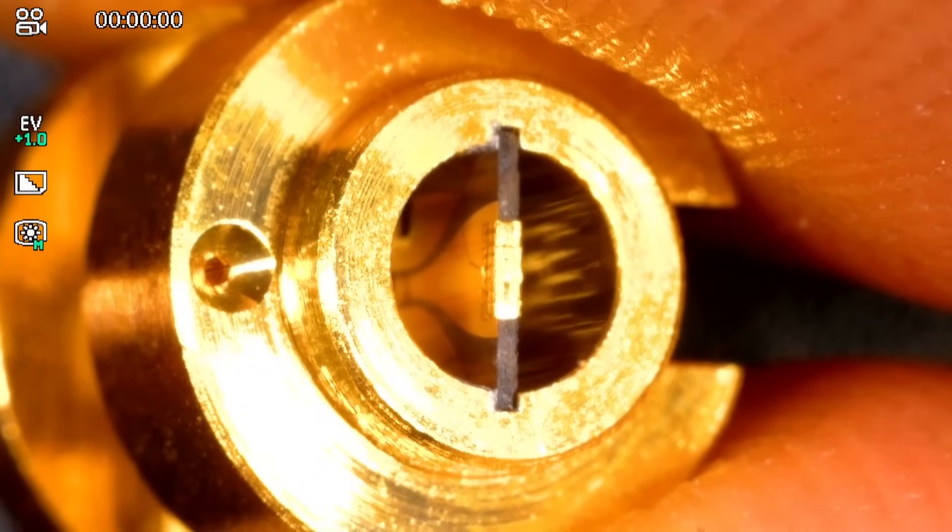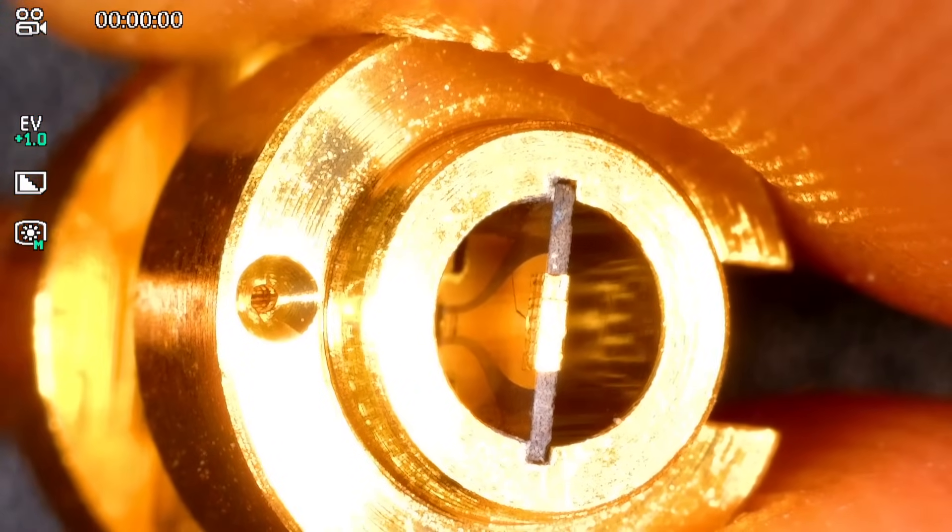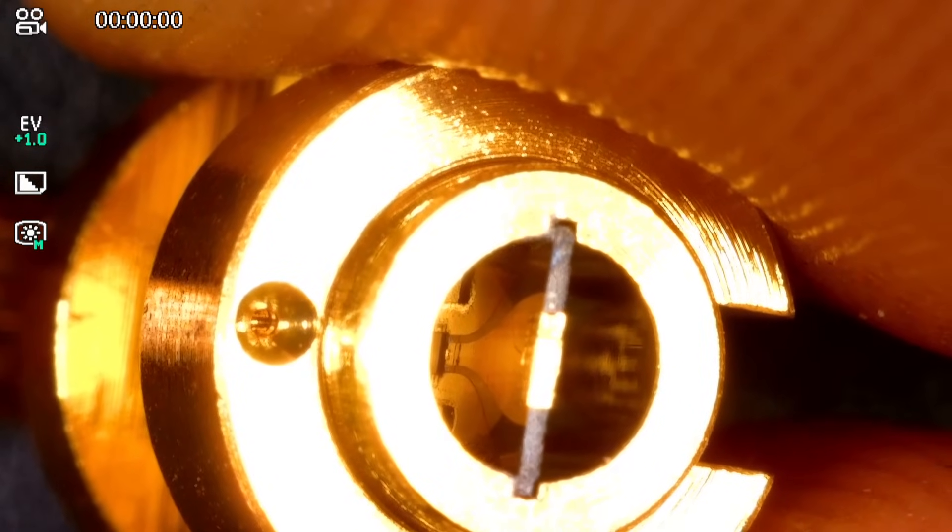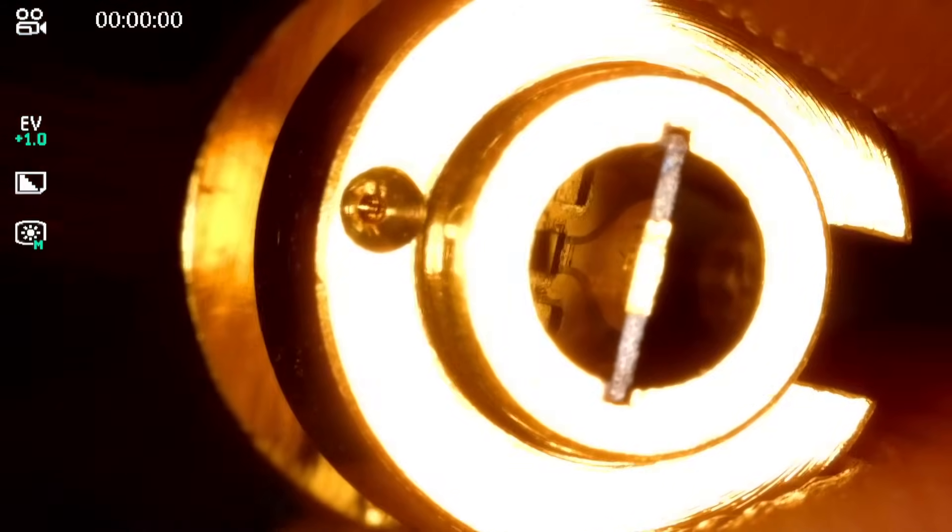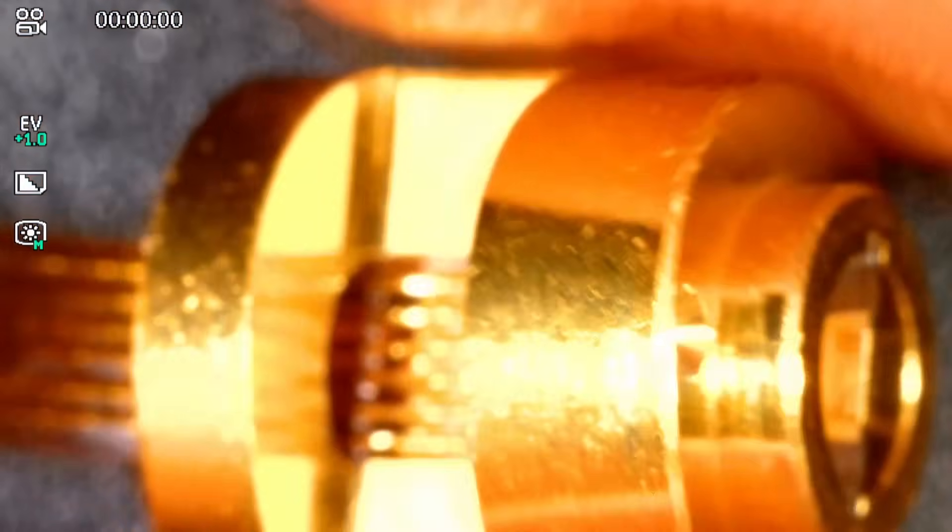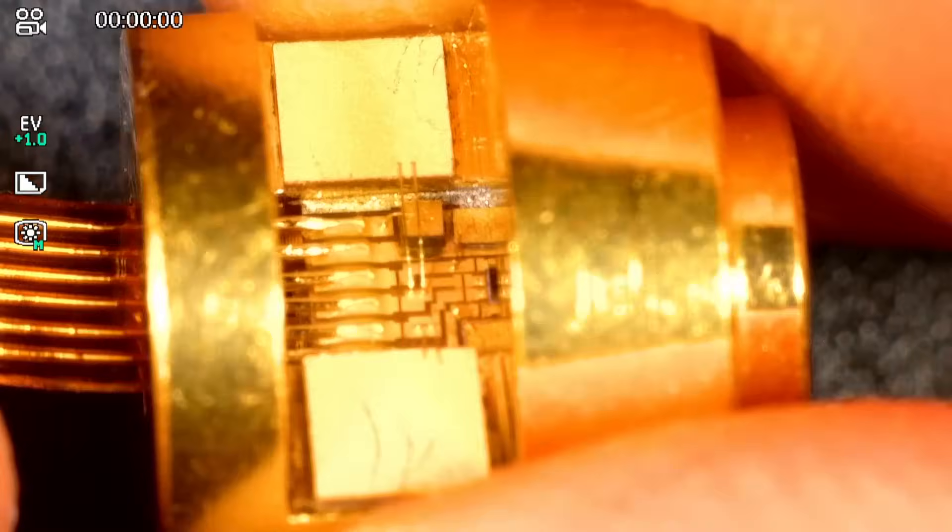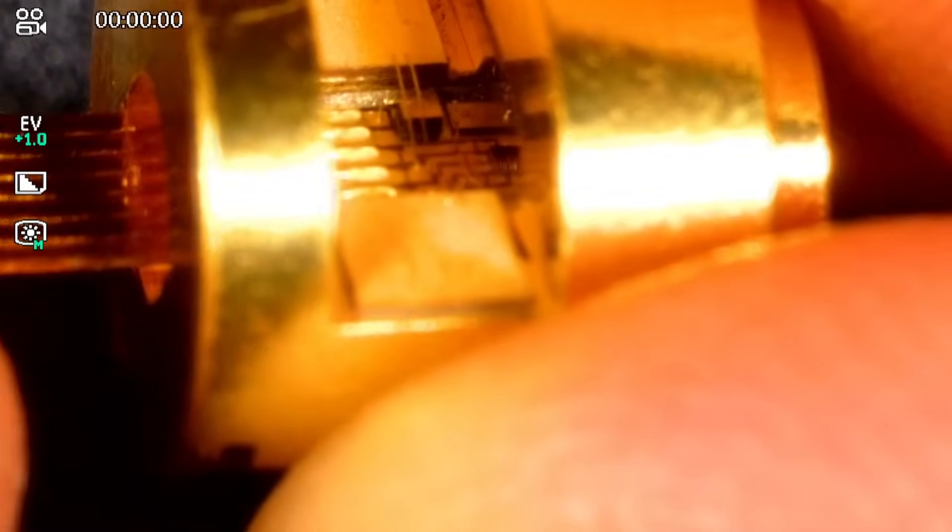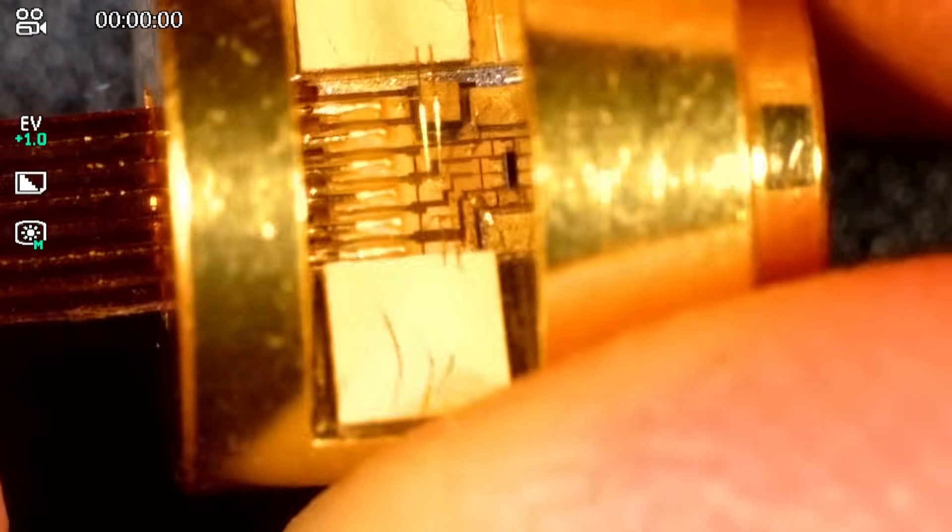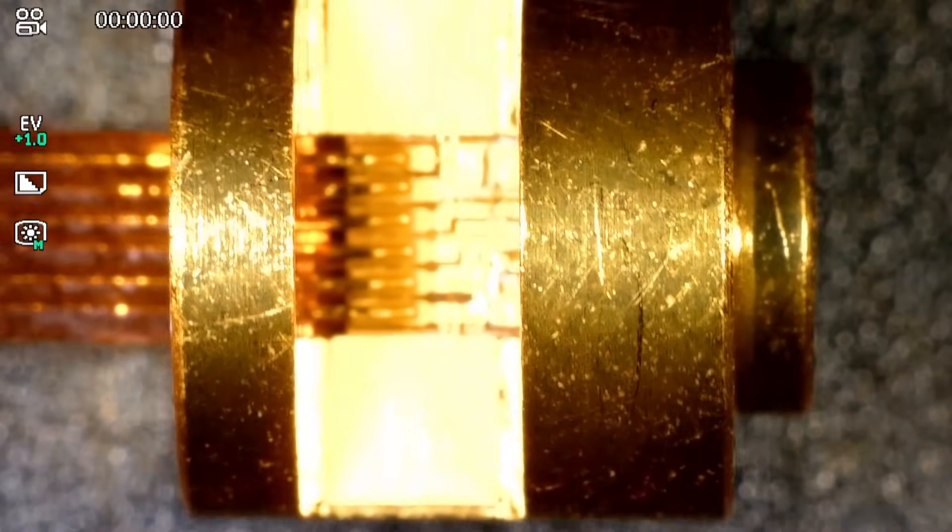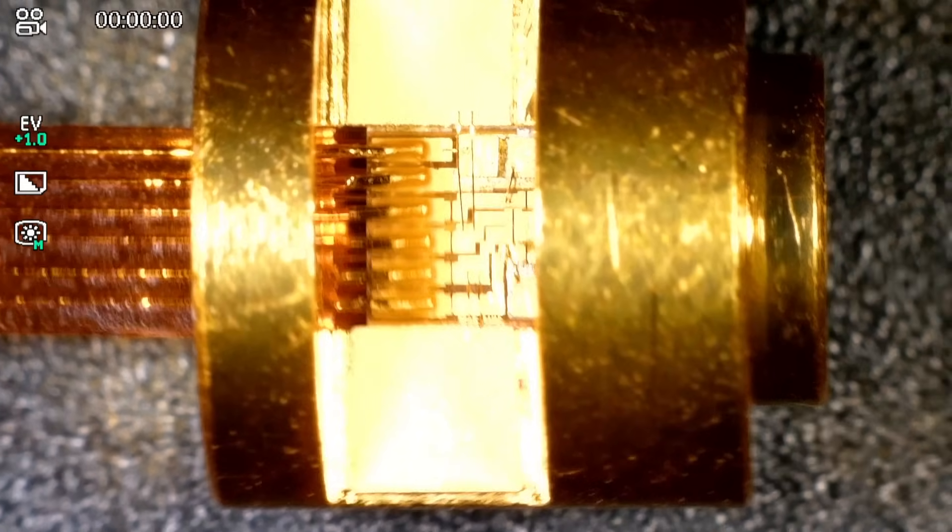If I tilt it a little bit, you can see better inside. That's our detector module over there. The contact to the detector is done from the front. If you look at this more carefully, there it is. That's where the connection happens from the outside of the coax. That transition thins out and ends up in a ground-signal-ground coplanar waveguide interface directly to our detector chip all the way on the inside. We should be able to pull this out of this chassis, but it's going to be a destructive process because these wire bonds are going to get torn apart when you pull this out.